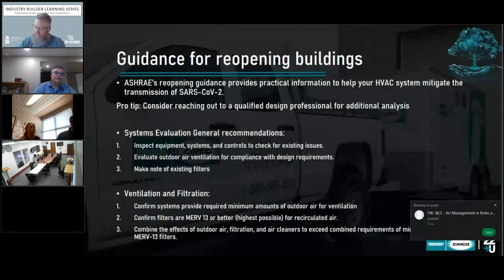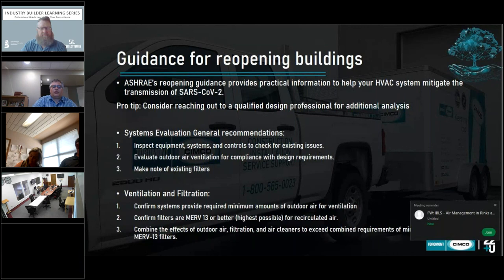Take a look at your filters. Are they MERV 13, or the highest achievable to meet the recommendation? And what are the combined effects of your outdoor air and filtration and air cleaners? Can we hit MERV 13? Can we make it higher? What are your needs? What are your wants?